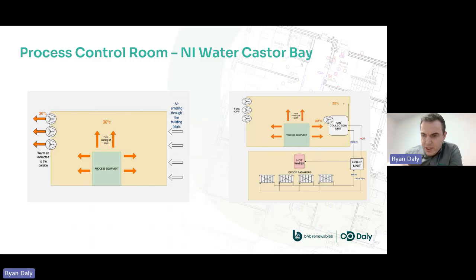So traditionally, when you think of ground source, you think of boreholes or horizontal pipework. But in this case, we're actually using a fan collector unit, and that's just simply a fan blowing air across the heat source. We're taking about 5 degrees out of that room, and that's helped to decommission a boiler in the plant room. That heat then is being used for their offices.